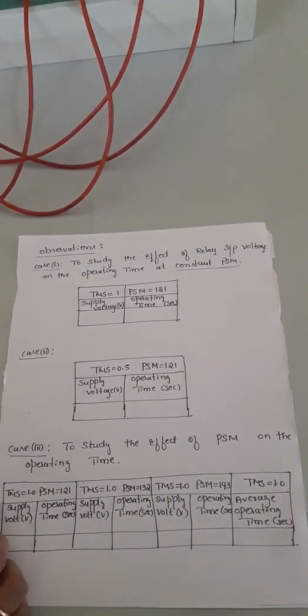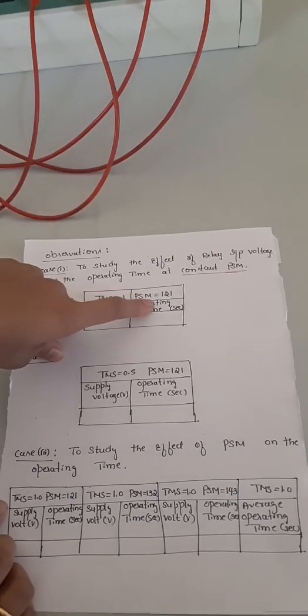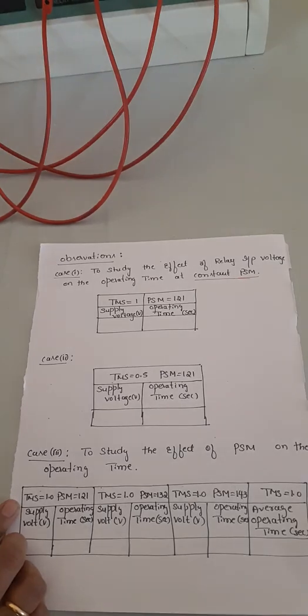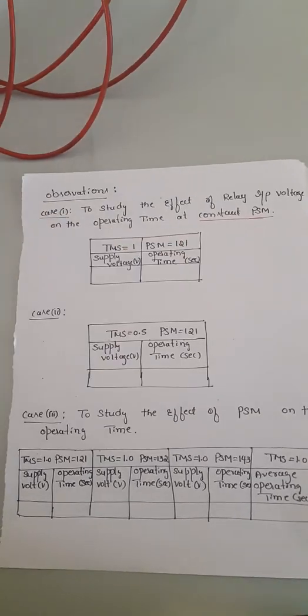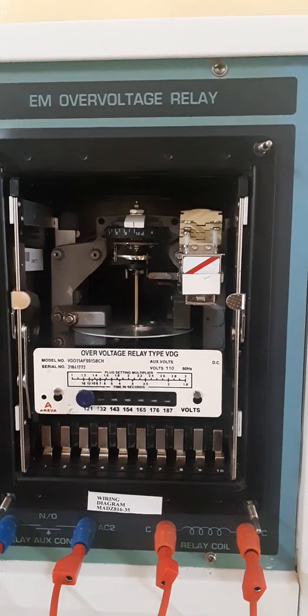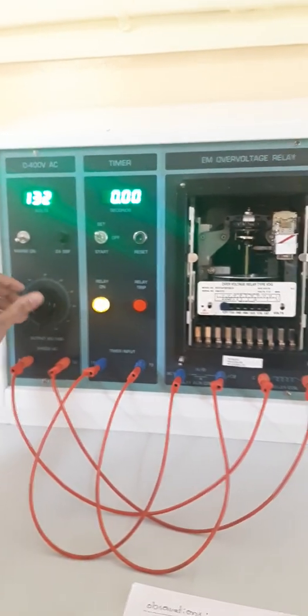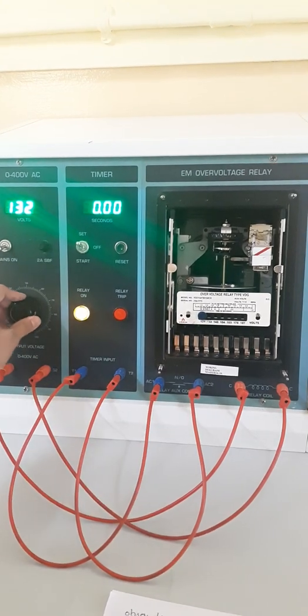Now for Case 1: we are studying the effect of relay supply voltage versus operating time. TMS is set to 1 and PSM is set to 121. The TMS value is also set to 1 and the plug setting to 121. Once these settings are made, we switch on the supply. The toggle switch is in set mode, and we vary the voltage using the variac. Since PSM is 121, the supply voltage must be more than 121V for the relay to operate.